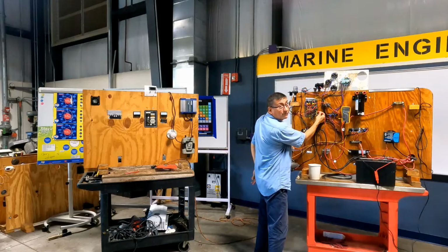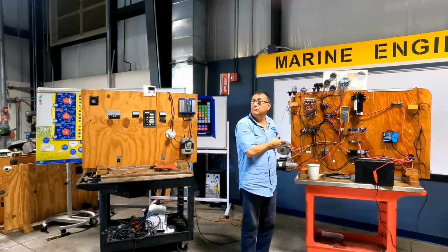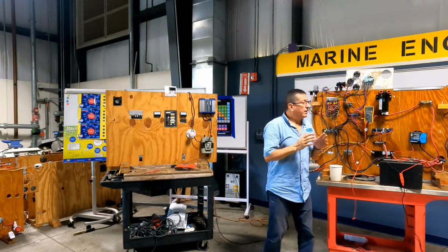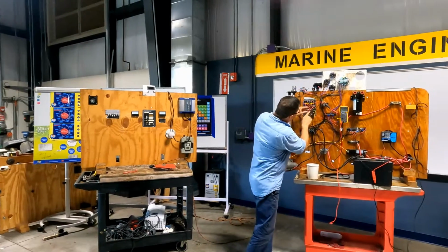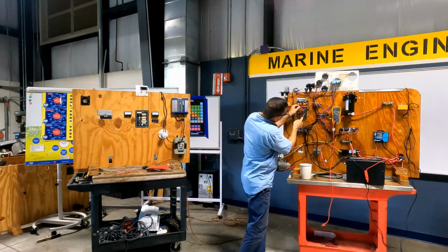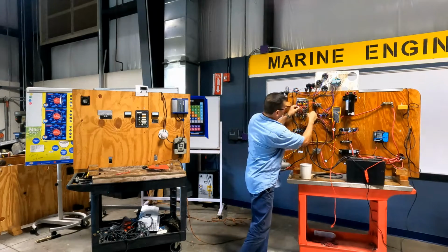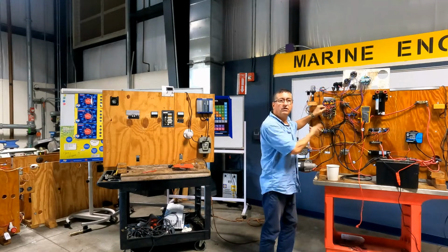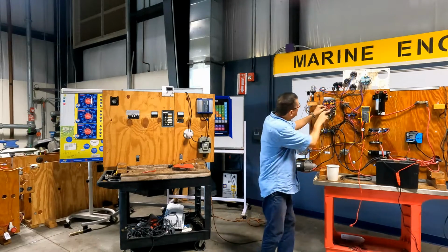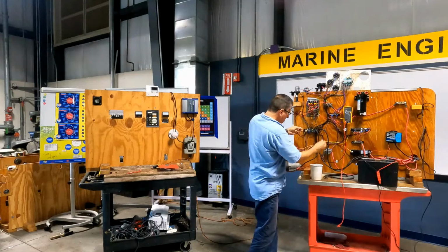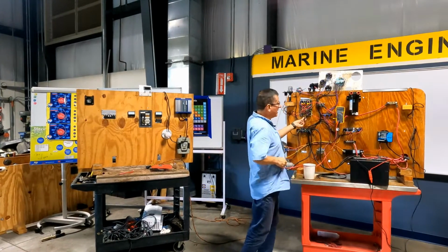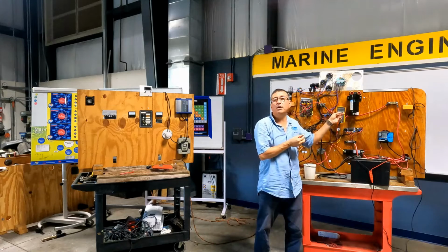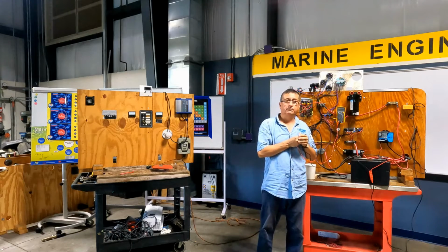2.3 amps. Nice, no? Okay. I need to interrupt the positive, because the positive passes from the positive bus bar into the output. This is the output going to the fan. I need to interrupt the positive, but I close the gap with my amp meter. In this moment, this is the amp meter.